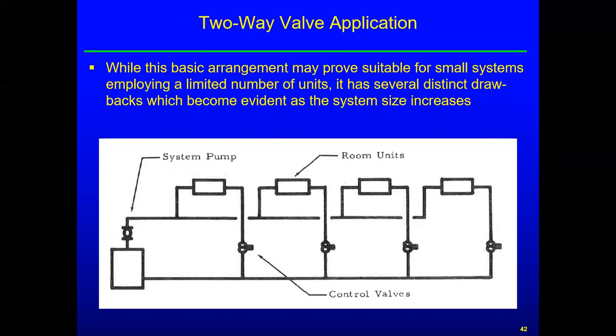Okay, while this basic arrangement may prove suitable for small systems employing a limited number of units, it has some problems or drawbacks as system size increases. And so you can see here, this is two-way control valves on a direct return system, because that first zone has very short supply and return piping. The zone on the far right has long supply piping and long return piping. So it's definitely direct return.